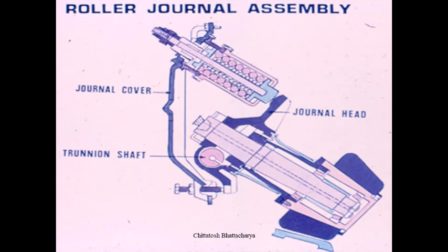Naturally, if the drying is not proper, then coal will stick on the bull ring segment. So according to the drying capacity, coal is supplied, and that drying is ensured by the mill outlet temperature, the coal outlet temperature from the mill, which is around 85 to 90 degrees centigrade.